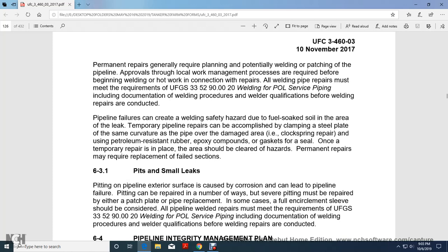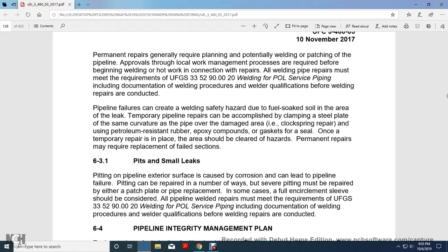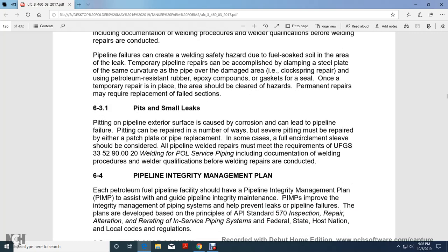with epoxy compounds, gaskets for a seal. Once the temporary repairs are in place, areas should be cleared of hazard. Permanent repairs may require replacement of failed sections. 6.3.1, pits and small leaks.